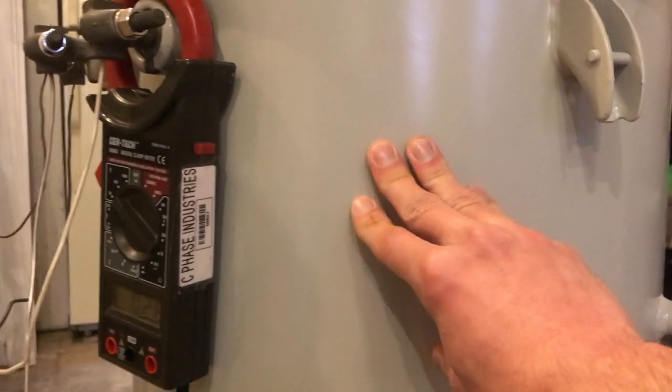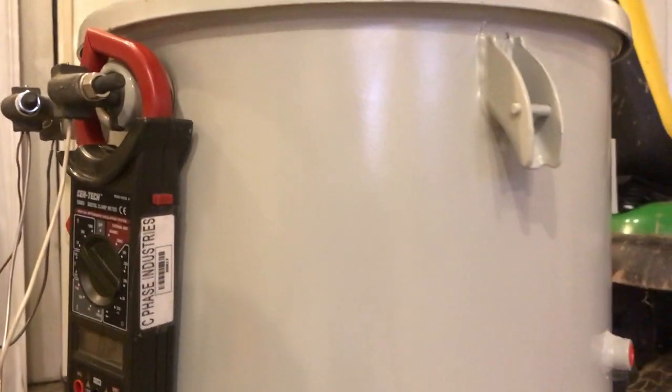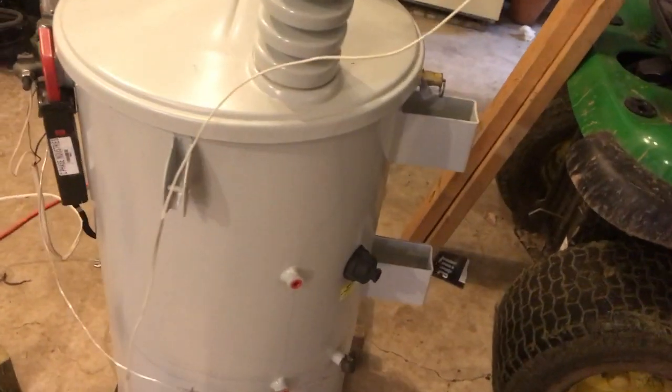I'll bring the microphone around. It definitely seems to be on the upper end of the transformer — from here up, it's just the way it sounds. Which is hopefully good, because that means it's not in the coil, hopefully. If it's in the coil, it's basically scrap.